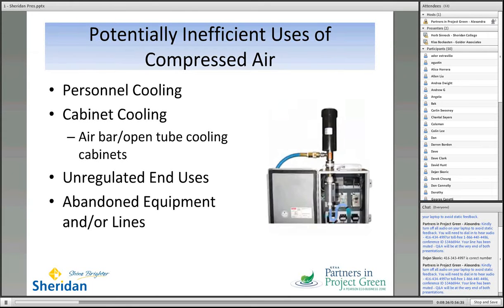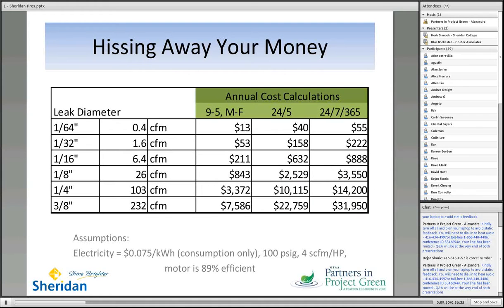And then there are some things like cooling people and cooling cabinets that should just be a fan. Why would you spend the money? Why would you spend $1.40 to cool somebody else? I think you could do it with a fan. And then the unregulated end uses. So the idea here is just, rather than having the open blowing and a hose, put a regulator on it, make sure you're controlling where that air ends up. And a lot of times in plants, we see that there's been a reconfiguration of equipment, that things have been moved around, or that some line of compressed air has been extended for future expansion. And yet that line is live, and if it has any leaks on it, it's basically wasting air. So those should be either capped or put a valve on it, something to keep air from flowing down that and potentially feeding leaks.